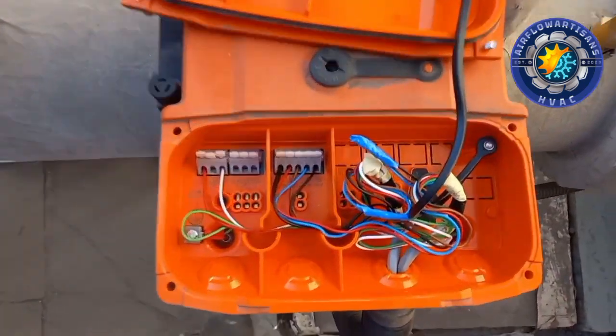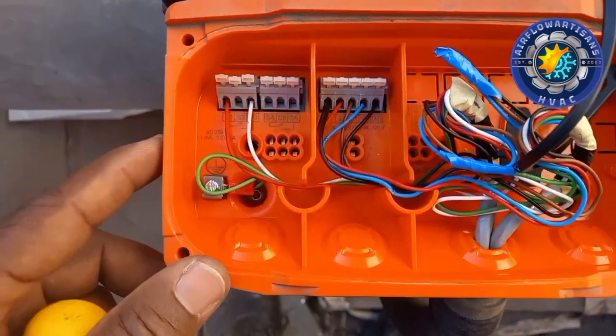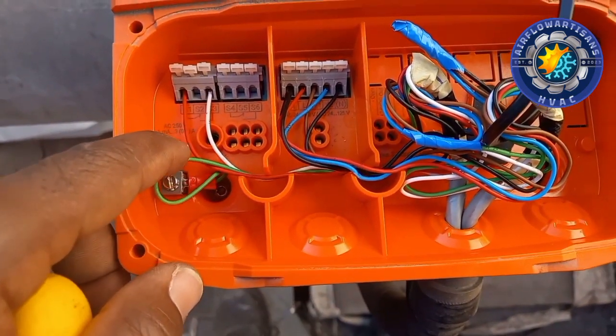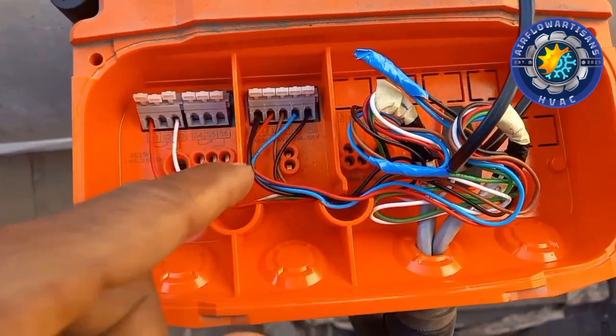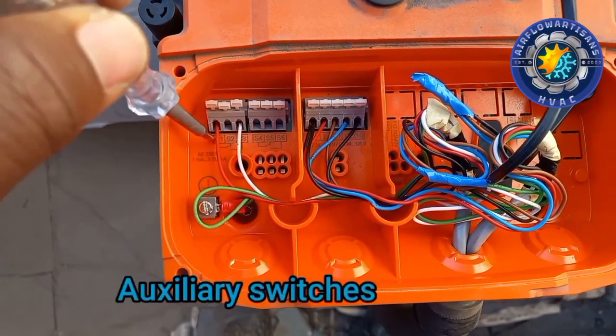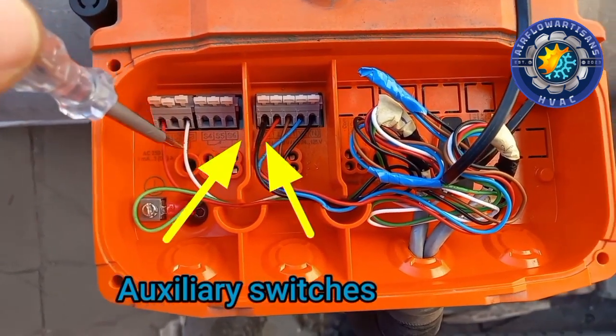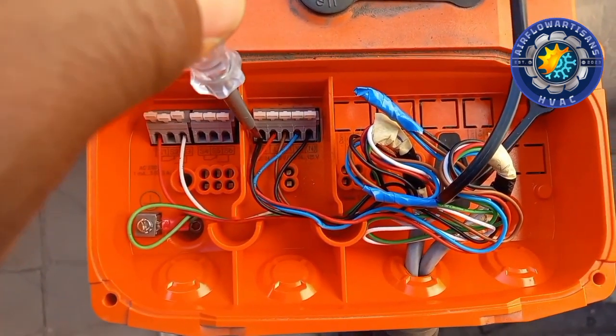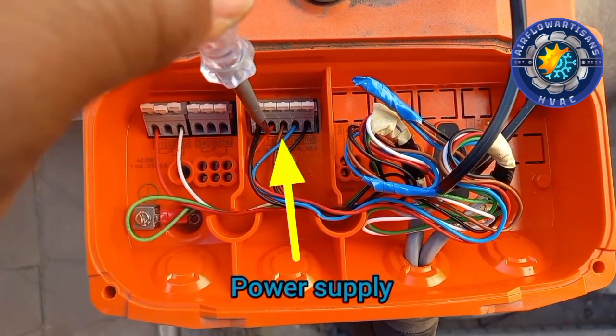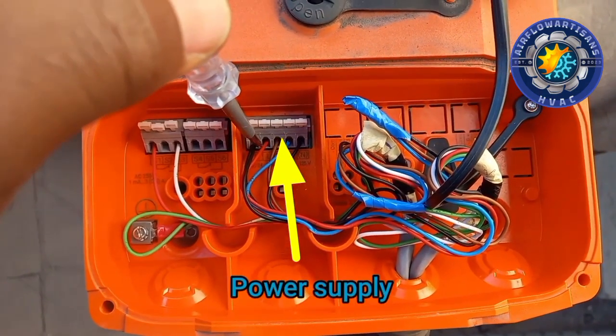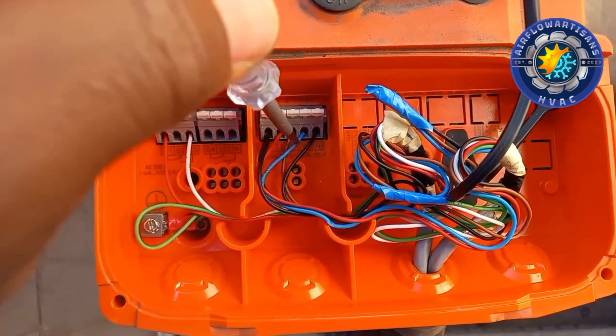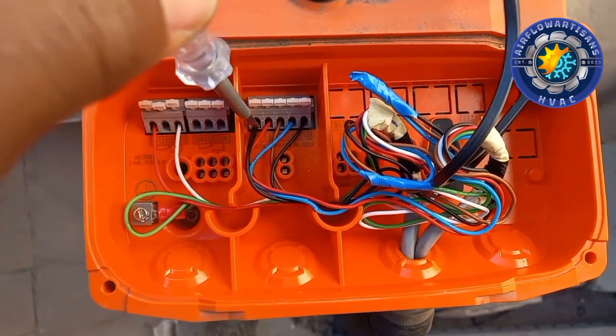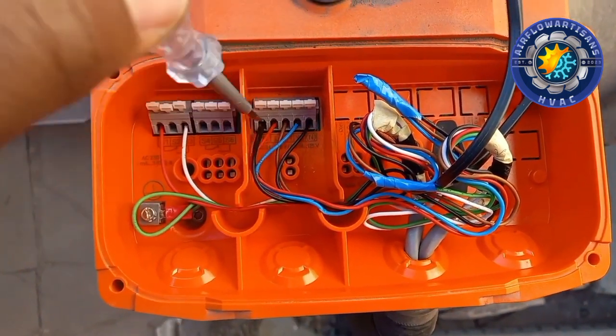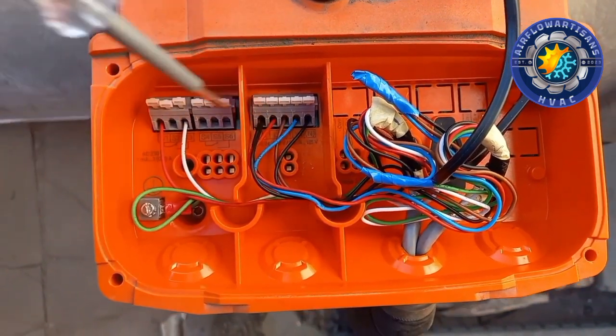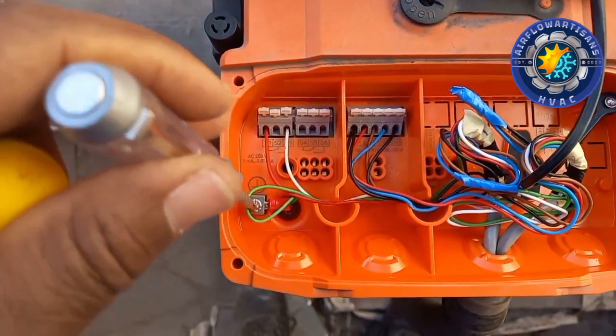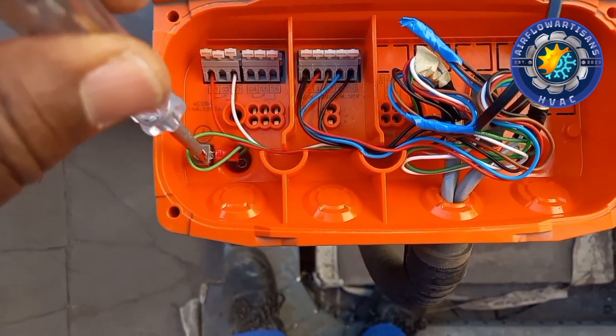So guys, this is the connection in this actuator. Here we have our feedback connected here, then our neutral here, our line or hot cable here, and this Y1 and Y2 are the command. The neutral cable is looped over here, and of course we have our earthing or ground cable connected.